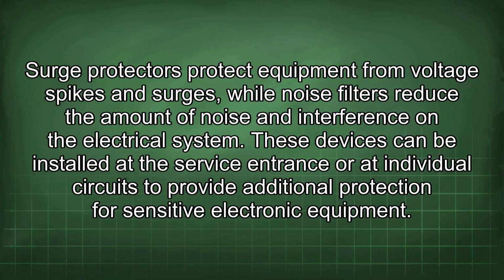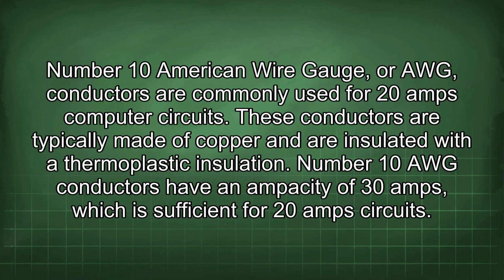Surge protectors protect equipment from voltage spikes and surges, while noise filters reduce the amount of noise and interference on the electrical system. These devices can be installed at the service entrance or at individual circuits to provide additional protection for sensitive electronic equipment. Number 10 American wire gauge, or AWG, conductors are commonly used for 20 amp computer circuits.